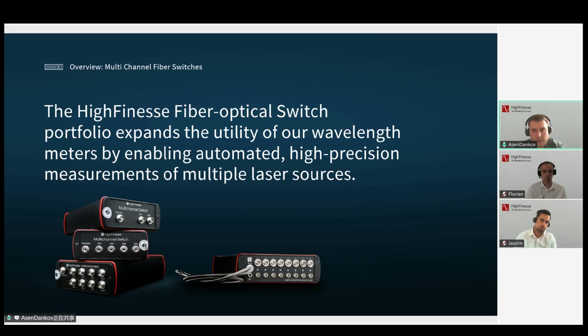Many research laboratories work with more than one laser. Measuring each laser with a separate wavelength meter is often unnecessary and can significantly increase both cost and complexity. Our multi-channel fiber switches provide an elegant solution to this problem. They allow multiple laser sources to be connected to a single high-finesse wavelength meter with fully automated switching between the channels. This makes it easy to monitor and characterize several lasers using one measurement system while maintaining the same high accuracy and reliability. Together with our wavelength meters, the switches form a flexible and scalable solution that can easily adapt as laboratory requirements grow.